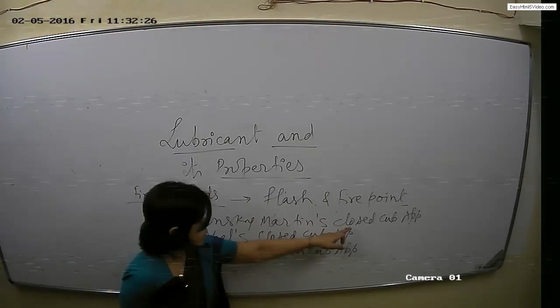Here in Abel's there is a water bath, and in Cleveland there is direct heating. This is a closed cup apparatus, so that's why there are some apertures. The aperture is for introduction of the thermometer, so we can note down the temperature of flash point and fire point. There is an aperture for the stirrer, to ensure uniform heating of the oil. There is an aperture for entry of the air. There is an aperture for entry of the flame, where you will introduce the flame for determining the flash and fire point. Since it is an open cup apparatus, no lid is there in the Cleveland open cup apparatus.